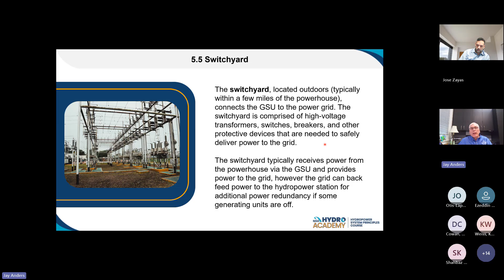Another key thing out in my switch yard is grounding, and this really comes back to safety. We want everything perfectly grounded to earth, so we have incredible grounding systems out in our switch yards and through our power plants. A lot of that comes down to safety - we don't want step potentials or ground rise potentials. Even the fence around these switch yards gets grounded so people don't get electrocuted when they come near our equipment.